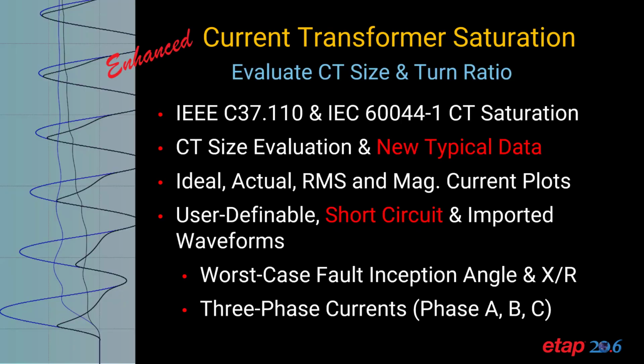The current transformer saturation analysis is an electromagnetic simulation which has been enhanced in ETAP 20.6. In this version, the symmetrical current and X over R from the fault current can be updated automatically into the CT saturation tool to determine the saturation effects and actually visualize the saturation waveform. So let's go ahead and see this in action.